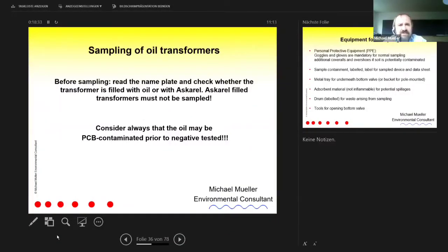So, sampling of oil transformers. Before sampling, always go and check the nameplate, because in 99% of cases you can find a hint on the nameplate. And the Askarel transformer, you must not sample, because that is clear: 60% PCB means 600,000 ppm. And always the other transformers, the oil transformers, may be positive. They may contain PCB. That means as a starting point, you consider them as PCB contaminated until the test says no.